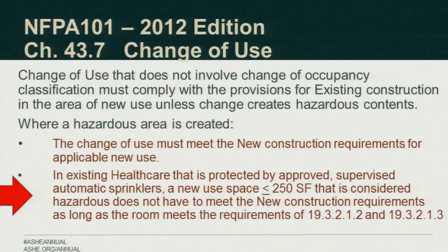Only if it's hazardous. So basically this is saying that if you have a change of use, you have to meet the applicable existing requirements, except if you're creating a hazardous area. Then you have to meet new, except if you're healthcare, less than 250 square feet, then you can meet existing.